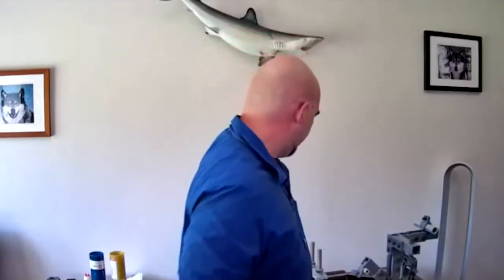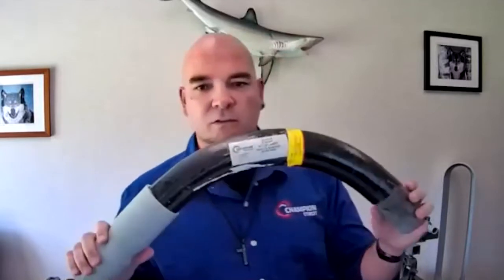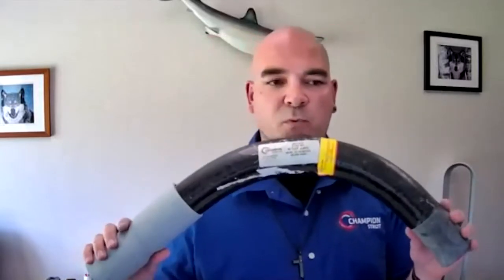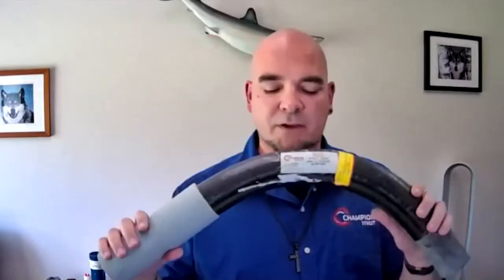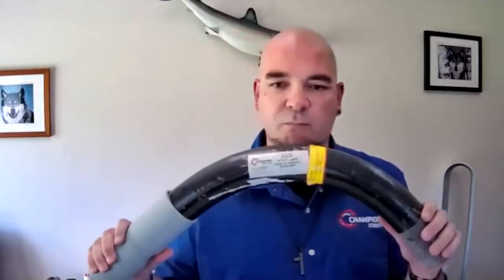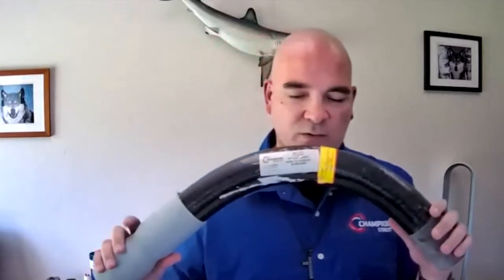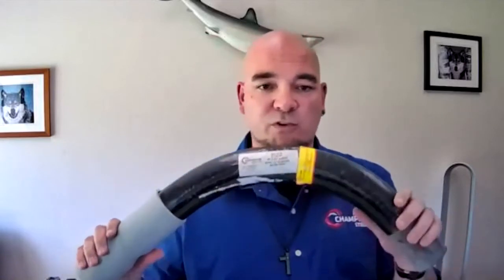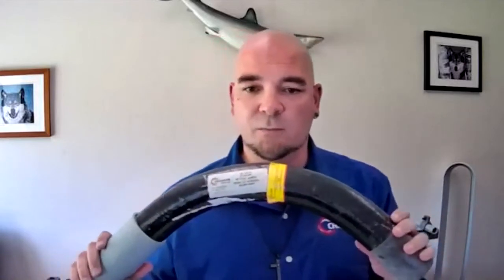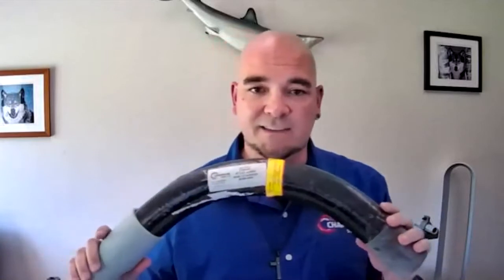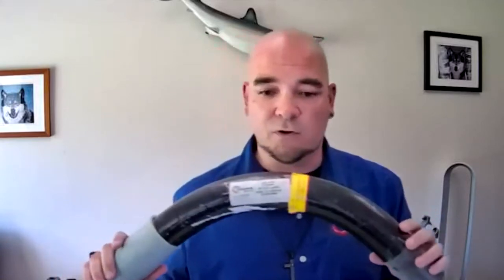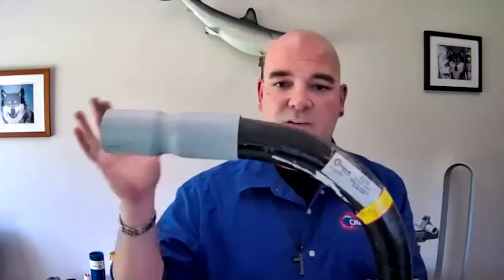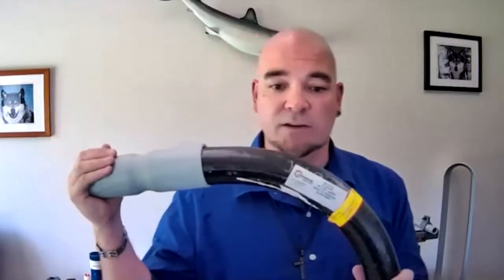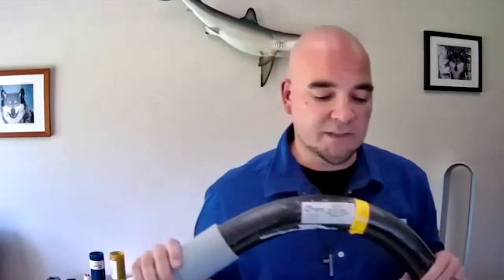Elbows, we do manufacture elbows. They have a very low coefficient of friction. They have a 0.38 coefficient of friction compared to that of GRC, which is a 0.55, or PVC, which is a 0.90. So you are able to pull and push your wires through our elbows at a much greater rate, eliminating the need for potential pull boxes or vaults. They can come with various fittings, PVC or fiberglass, whichever you would recommend for your application.